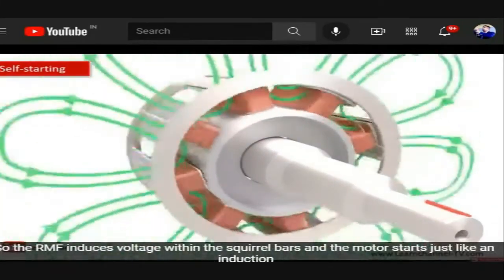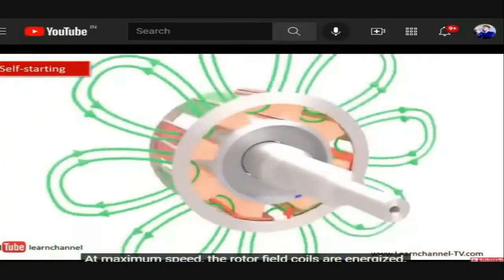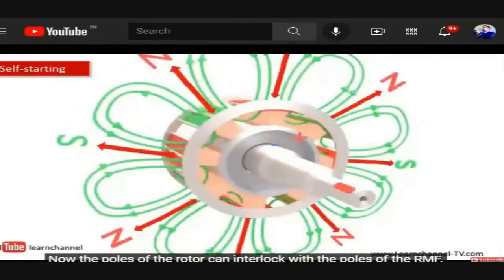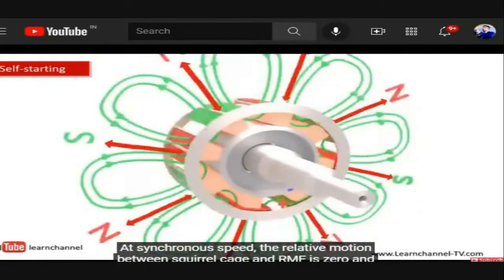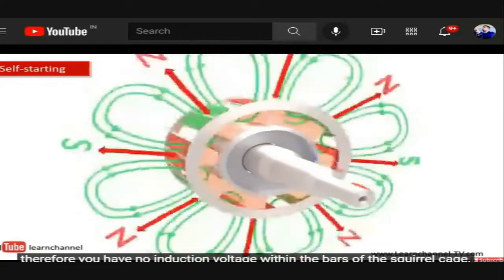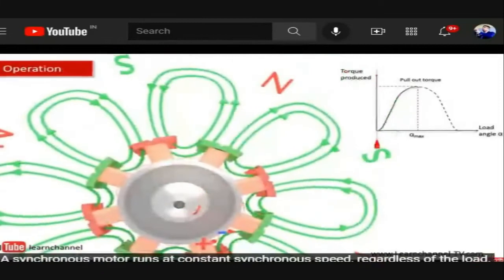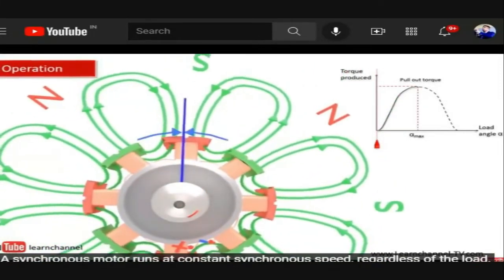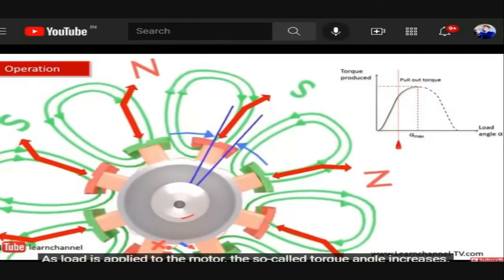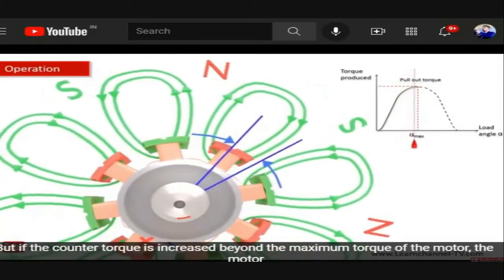A squirrel cage is fitted within the pole tips so the RMF induces voltage within the squirrel cage bars and the motor starts just like an induction motor. At maximum speed, the rotor field coils are energized and the poles of the rotor interlock with the poles of the RMF at synchronous speed. The relative motion between squirrel cage and RMF becomes zero, so there is no induction voltage in the squirrel cage bars, and synchronous operation is unaffected. As load is applied, the torque angle increases but speed remains constant.